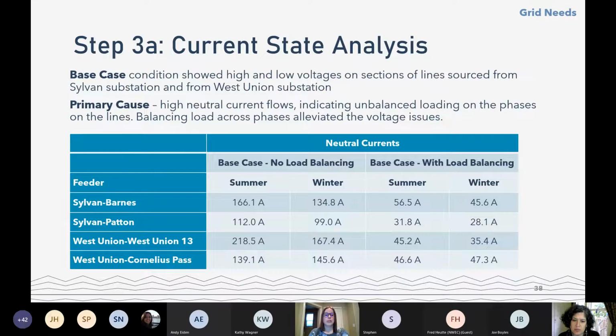Our current state analysis showed high and low voltages on sections of line sourced by Sylvan and West Union substations, primarily due to high neutral current flows. This happens when new housing developments are added to lines that have three wires on the pole, one per phase, and residential developments end up attached to the same phase instead of being balanced across all three wires. This causes unbalanced loading, and we have to take steps to move load to a different wire.